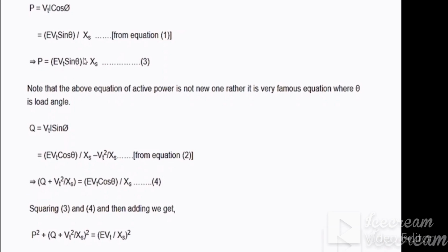So you know that these are dependent on the field parameter. How? Your active power consists of this capital E. This capital E is nothing but the no load induced voltage in the armature conductors, and that induced voltage depends upon the air gap flux. That air gap flux can vary, and how does it vary? It depends upon the field current.